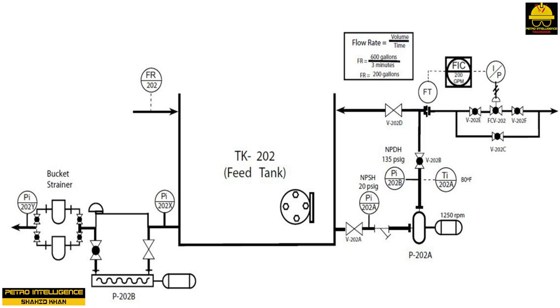3. Check pump lineup and tank levels. Identify valves that need to be open and shut. 4. Open pump suction valves and fill pump. Be sure all of the valves between the pump and the tank are open. 5. Open pump discharge valves. PD pumps should never be started with the discharge line closed.